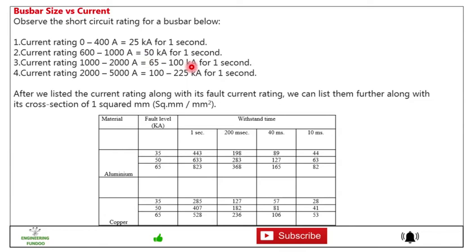Current 600 to 1000 amp, 50 kA for 1 second. So these are the short circuit current rating and ranges, and it is most important for the busbar to withstand the short circuit current. After we listed the current rating along with its fault current rating, we can list them further along with its cross-section of one square mm. So here for materials aluminum we can see the fault level.